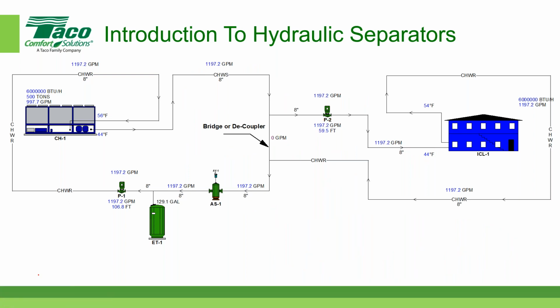Yeah. So if the pressure drop across the bridge, and again, that's from this point here to this point here, let's say that the delta P, oops, that's supposed to be a P, is some significant number. And since we're not going to talk about specific numbers, let's just say the delta P is high. Well, in any hydronic circuit, you always have to have a balance in the pressure drop. So if the pressure drop was high, now I'm going to assign an arbitrary value.